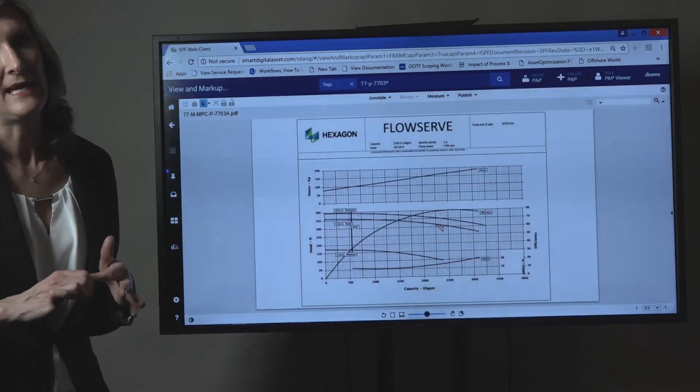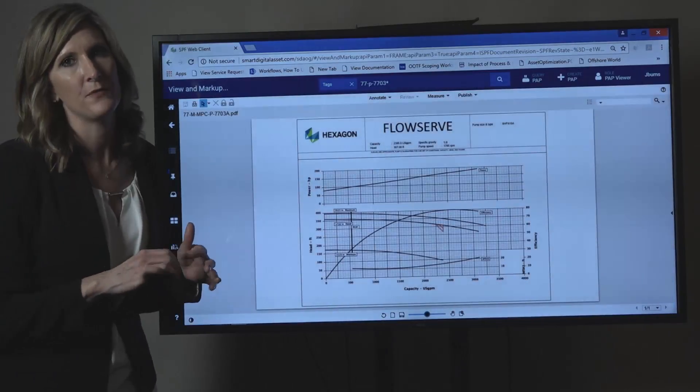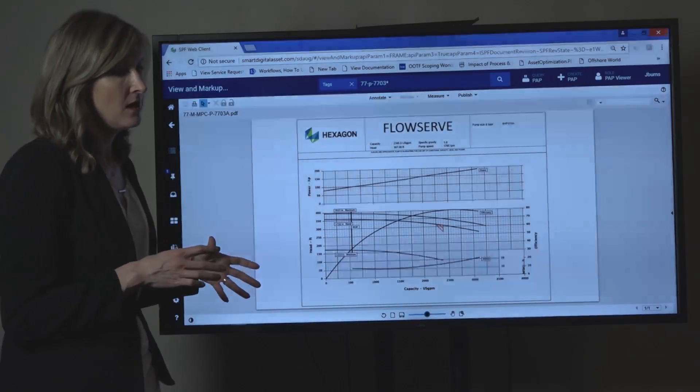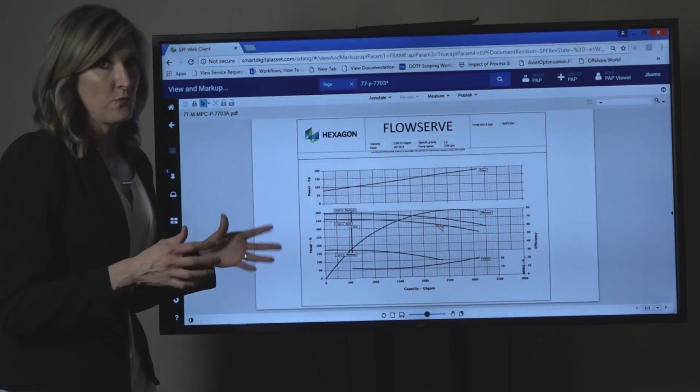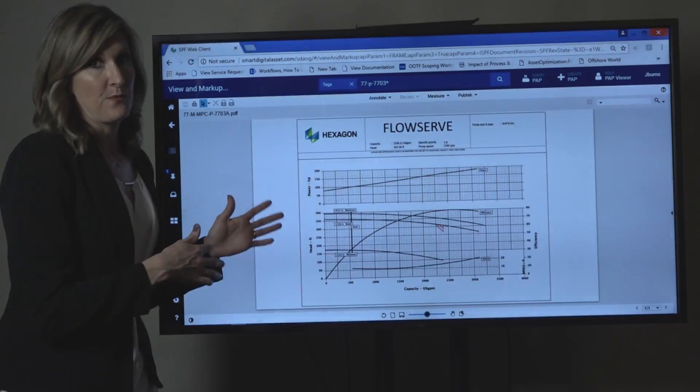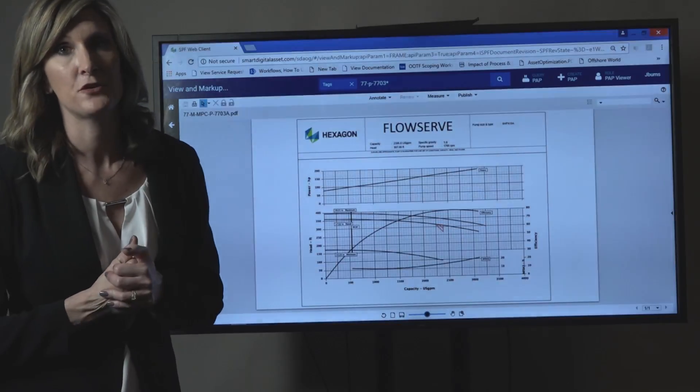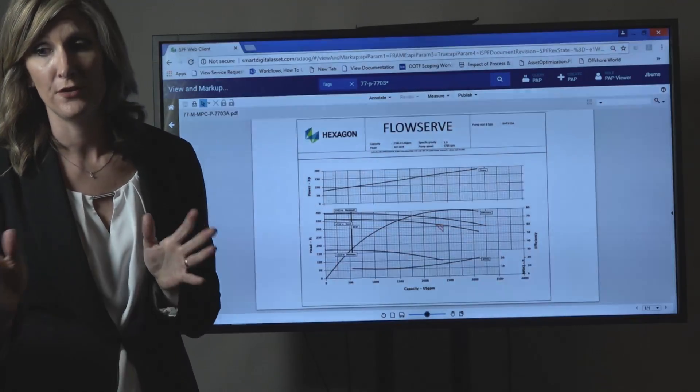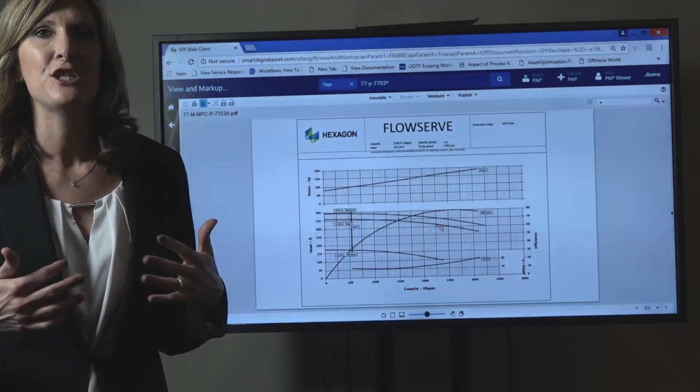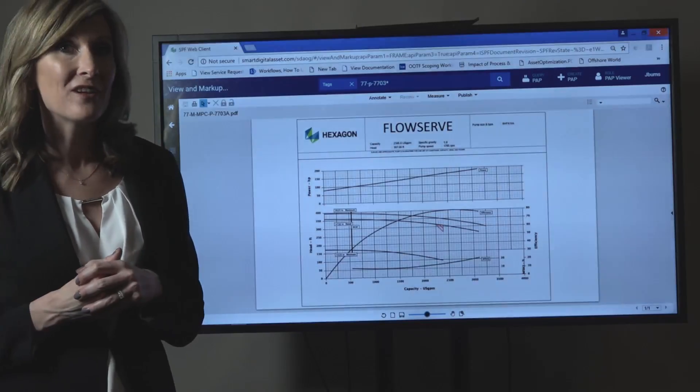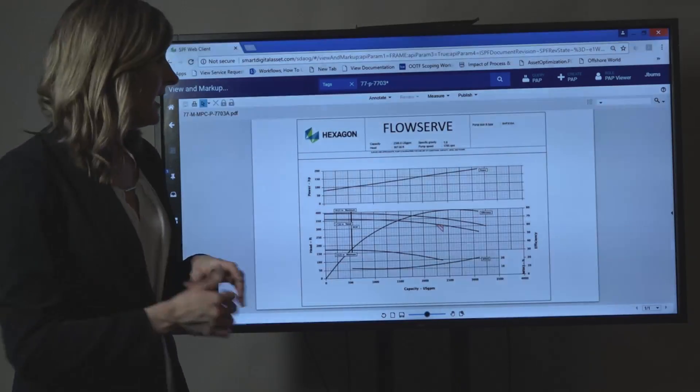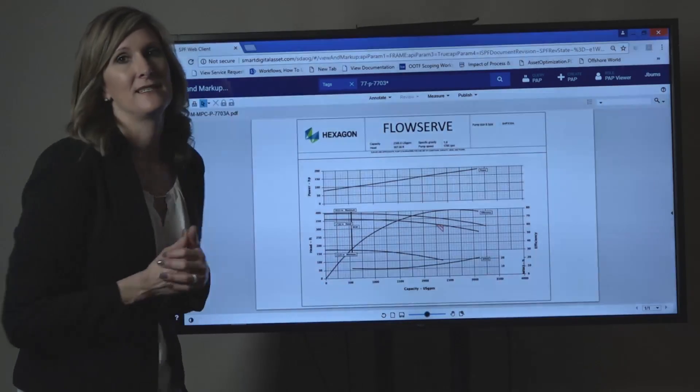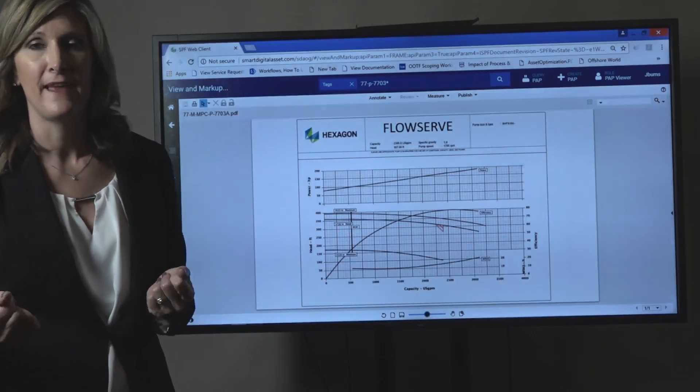Imagine if the data sheet and the pump curve were available to you in the field. So you grab your PPE, you grab your tablet, you go out into the field. You open the data sheet, you open the pump curve. You look down at the discharge pressure, you look at the flow. You have all the indications of where it's currently operating, and you can plot it against what it was designed to do right there.